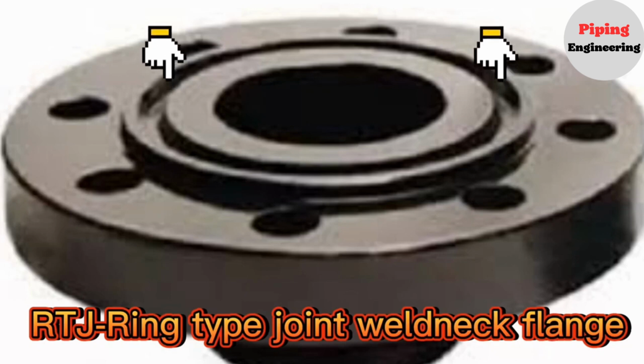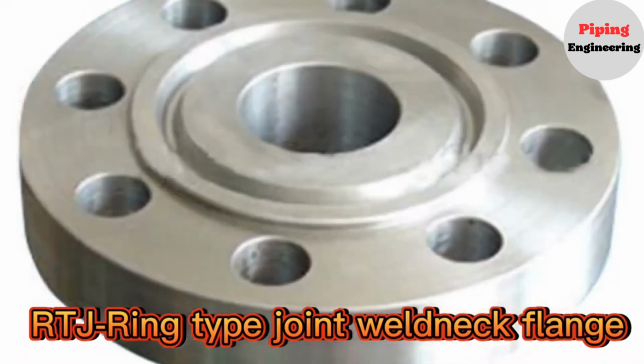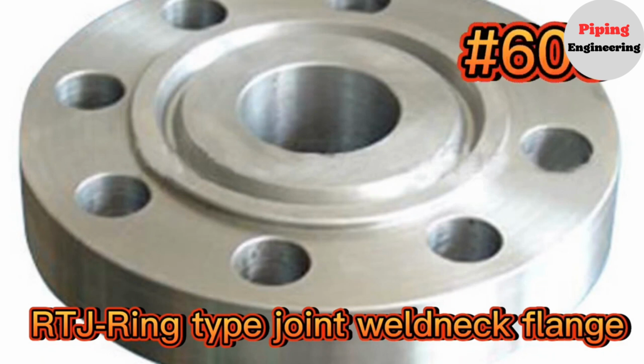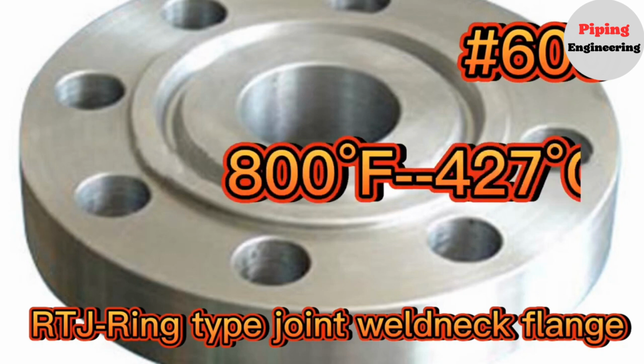This compression results in a leak-proof, close-fitting seal on the pipe or connection. The RTJ flange is designed for high-pressure and/or high-temperature pipeline applications. The RTJ flanges are usually preferred for class 600 and higher ratings and/or when service temperature exceeds 800 degrees Fahrenheit, 427 degrees Celsius. A ring-type joint flange is substantially different from other types of flanges used in the piping and pipeline industry.